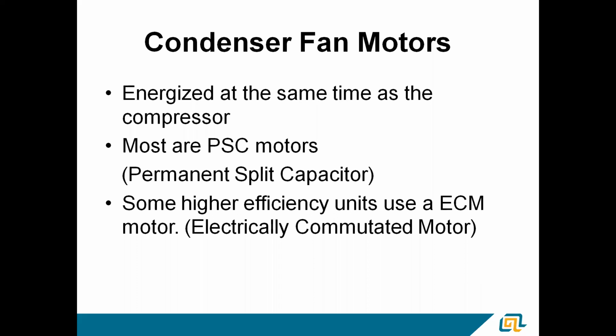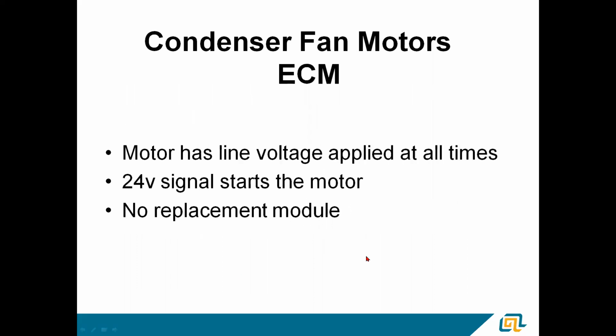Basically, those units will have line voltage applied to them at all times. So you got a 240 volt or 230 volt system. That motor's always got that voltage sitting on it, waiting for a command to run. Then there's a 24 volt signal that actually starts the motor. That signal will tell the motor when to run. It's usually in parallel with the contactor. So 24 volts is sent to the contactor, pulls in the contactor, gets the compressor running, and it's also sent to that motor to tell it to turn on.